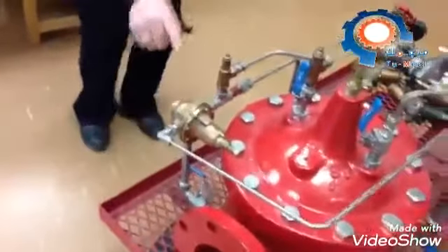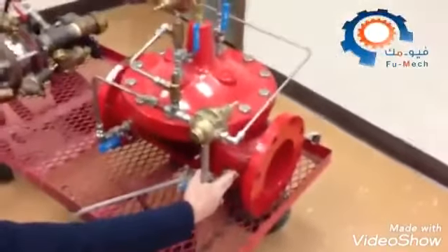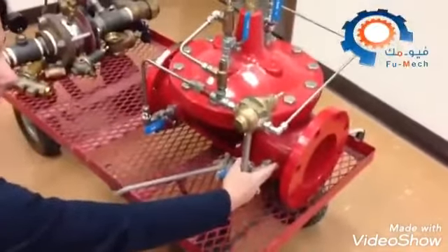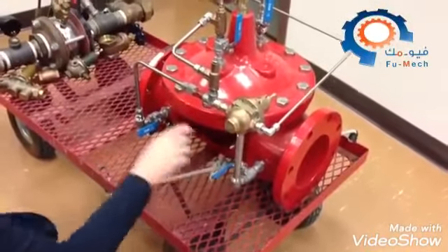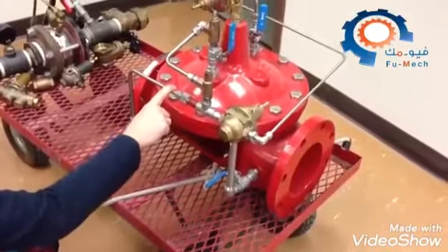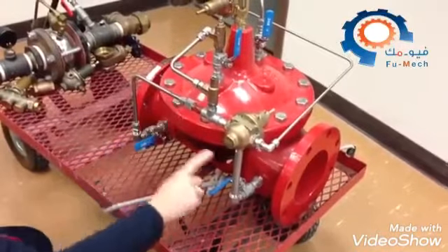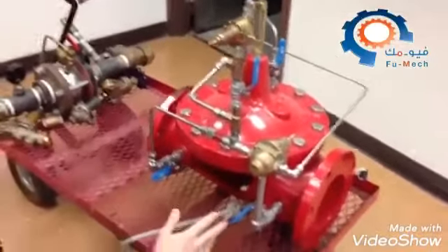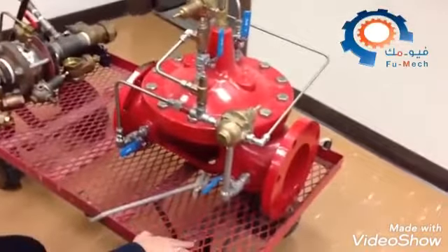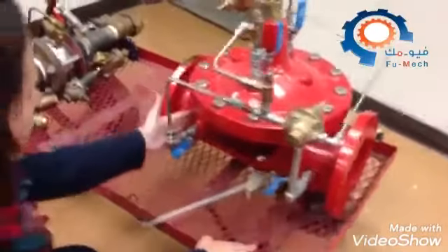Your CRD in this application is always going to have a larger pipe leading to the downstream side, the lower pressure side, because it needs to be able to take off more water than this can put on. So that's another indicator of which is upstream and which is downstream. So here's the idea. Here's your upstream side.